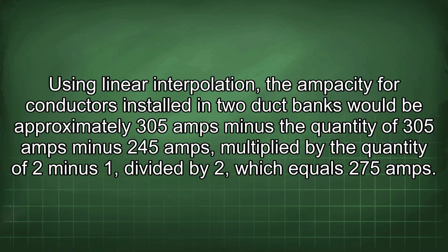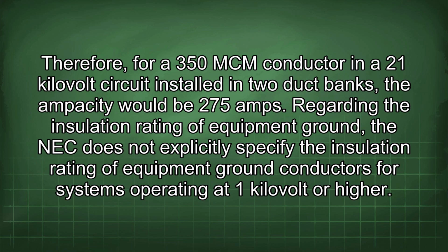Using linear interpolation, the ampacity for conductors installed in two duct banks would be approximately 305 amps minus the quantity of 305 amps minus 245 amps multiplied by the quantity of (2 minus 1) divided by 2, which equals 275 amps. Therefore, for a 350 MCM conductor in a 21 kV circuit installed in two duct banks, the ampacity would be 275 amps.